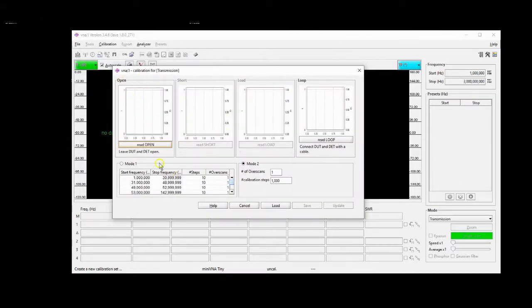The first thing it wants is an open. Now, as you recall, the 2 cables that I have connected up to my miniVNA Tiny were nicely spaced from one another, and I am going to choose mode 1, which takes a little bit longer to do. I have set this up so that the range of frequencies I'm interested in has a lot of calibration steps and overscans to give me the best accuracy I can possibly get. So here we go. We're going to read the open.